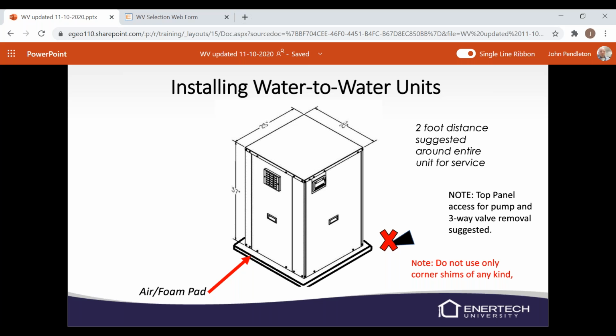And for one, it's just not a good look, and then the unit's not level. So with the rubber pad, it's not going to sag over time. It'll keep that unit level. And it'll also help if there is any kind of vibration. The air foam pad will help as well, but the rubber pad definitely will help with any kind of vibration being transmitted into the floor from the unit itself.